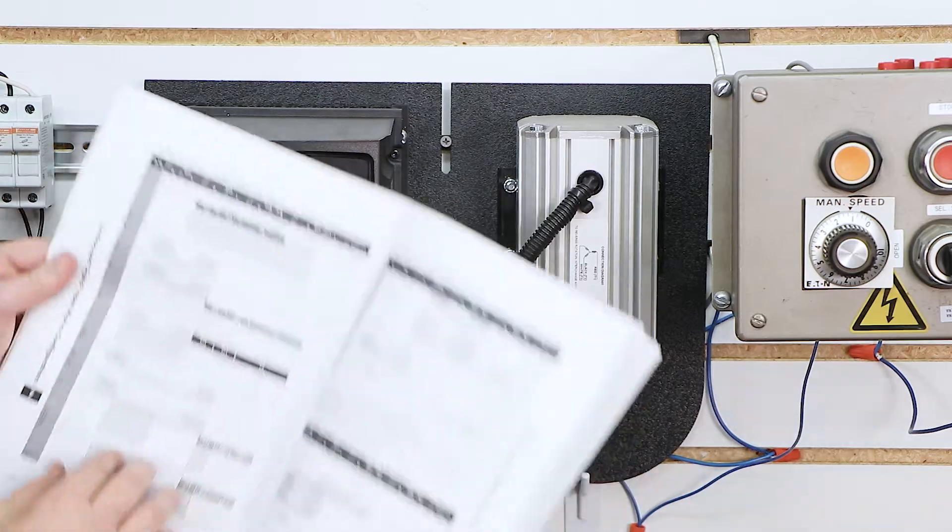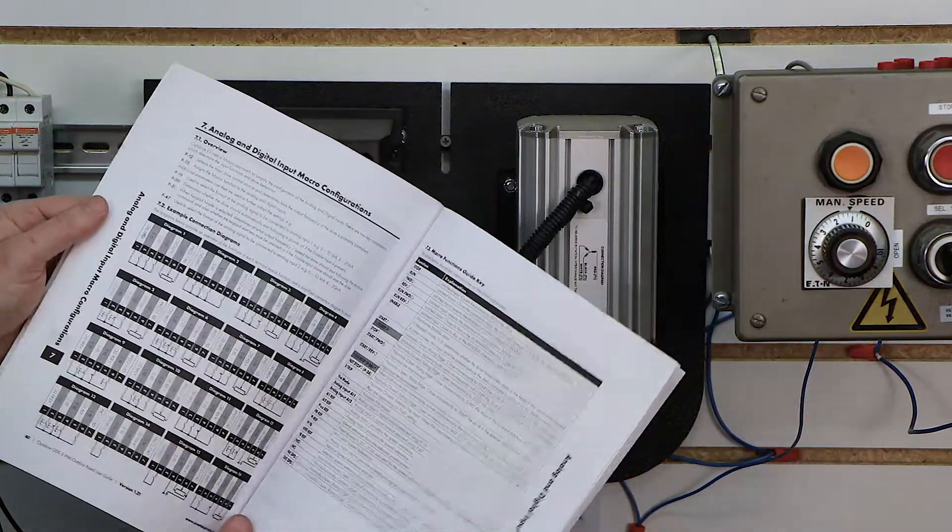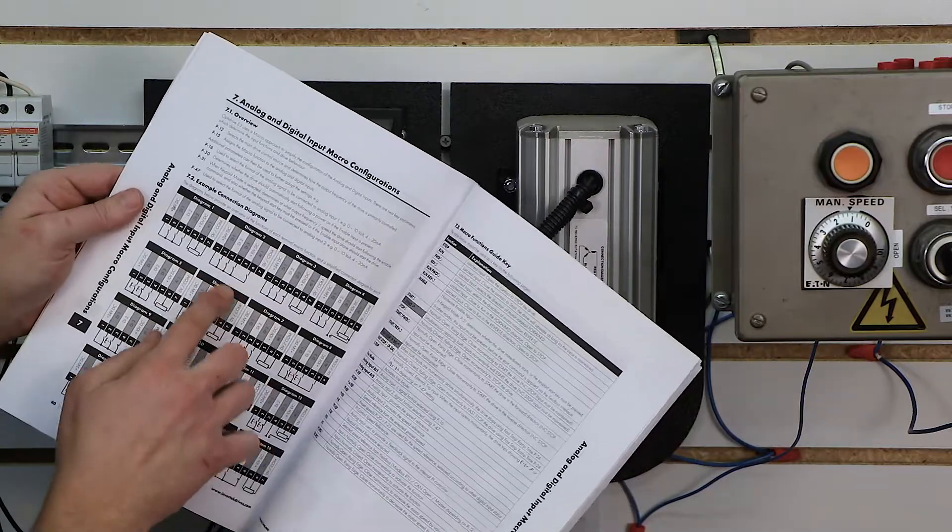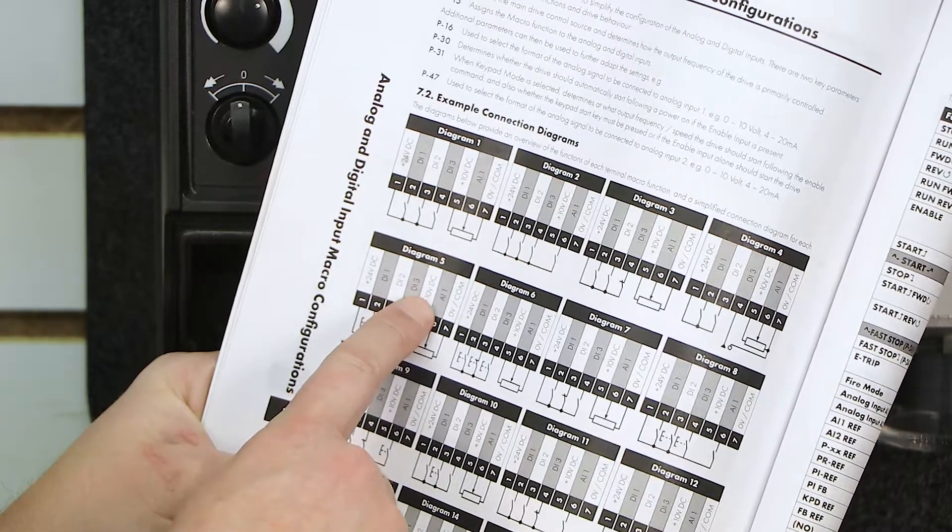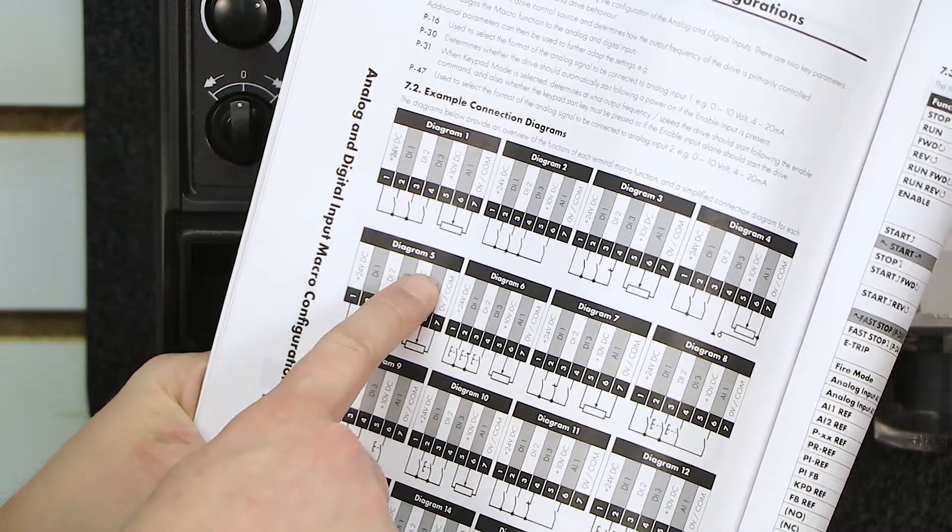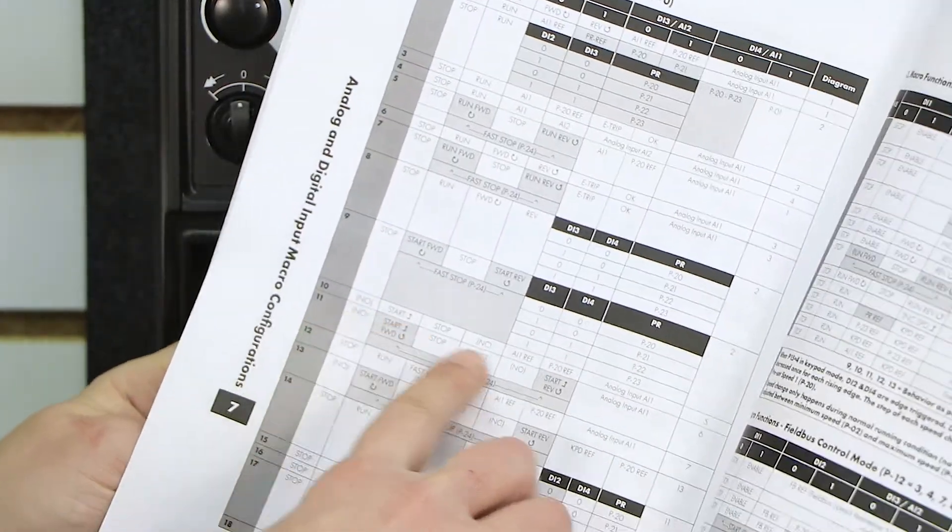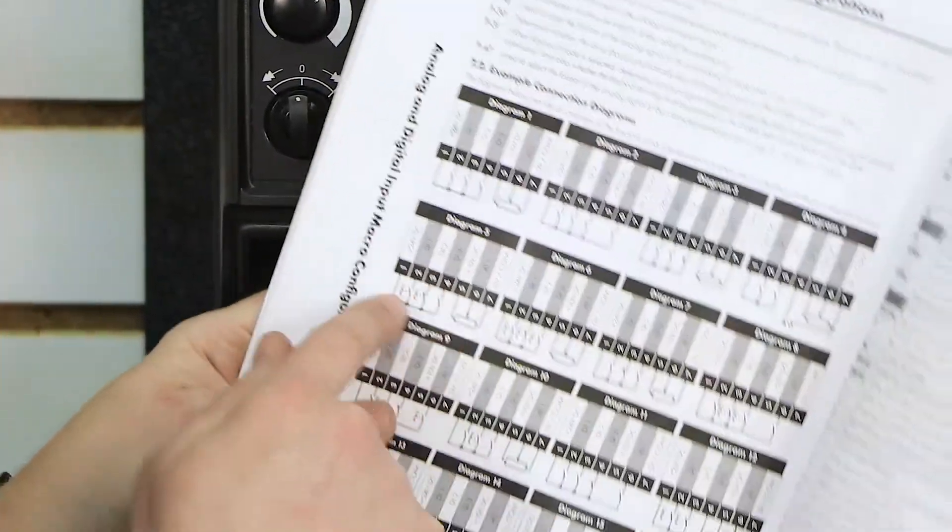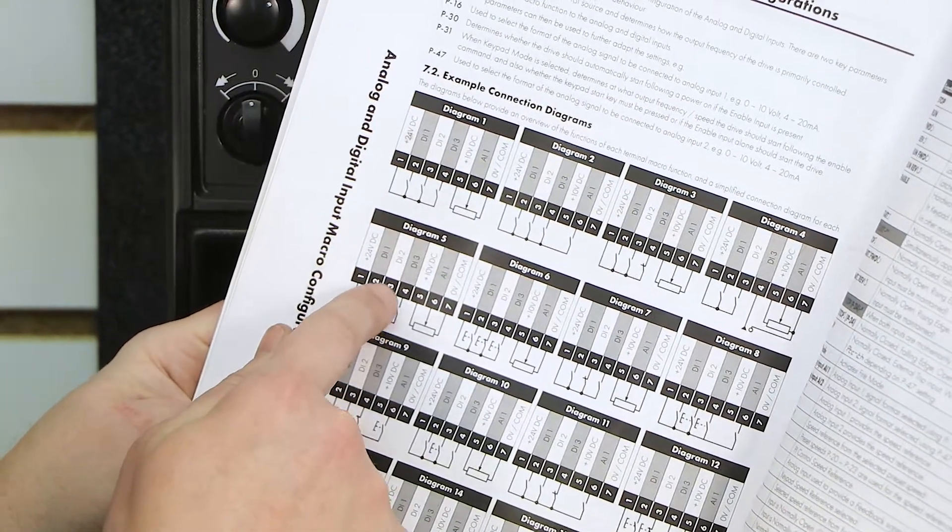If I go back two pages on my manual, or actually back one page, you'll see an electrical diagram of each of those macro settings. And we're going to be looking at diagram 5. Now you may be wondering, diagram 5, but we chose 10. But on the right hand side of that column, for that macro, on the far right you actually see which diagram it corresponds to. So diagram 5 has a normally open push button for input 2, and a normally closed for input 3.